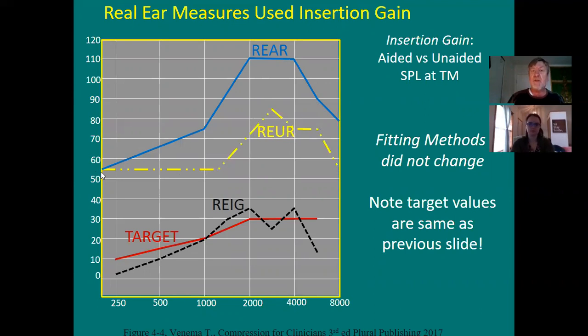If the input sound was 55 dB, because that's what they do, make it like regular speech, the tone sweeps a few times, and now you're getting the unaided ear canal resonance. Then they would hold that tube firmly in place and put the hearing aid gently on top of the tube, turn the hearing aid up to a comfortable volume, and have the same sweep tones come in at 55 dB, same intensity.